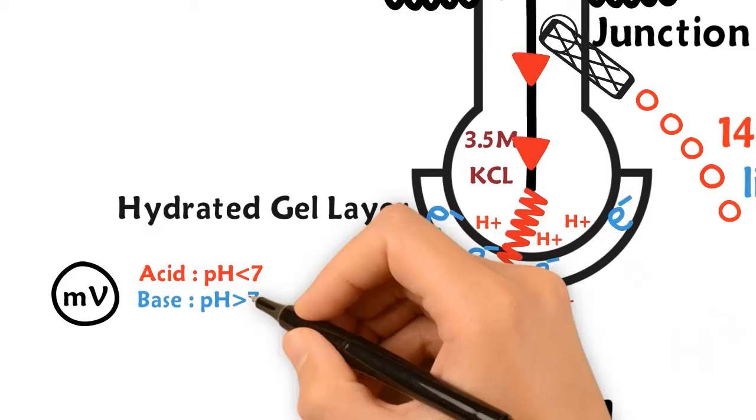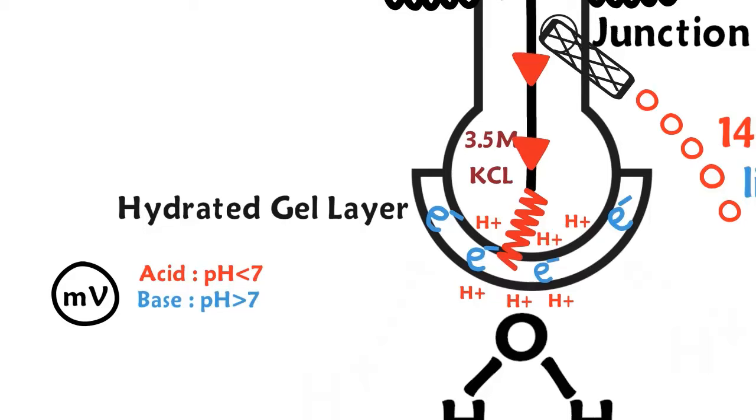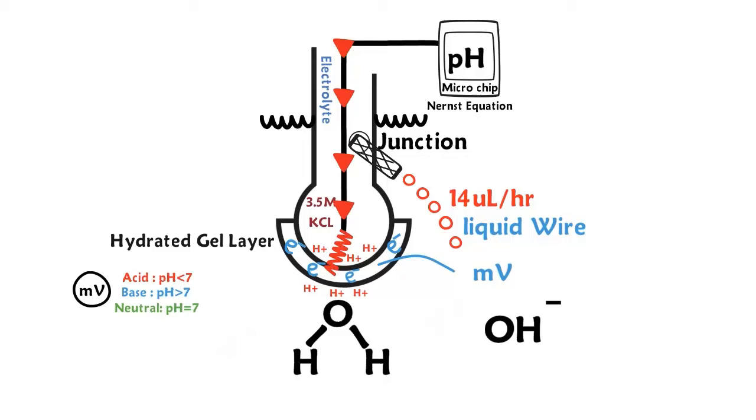Equal hydrogen ions on both sides of the gel layer and glass bulb will create a neutral pH value. This is created by a millivolt charge close to zero. Based on the number of hydrogen ions in this example, we would expect about an 8 millivolt charge.